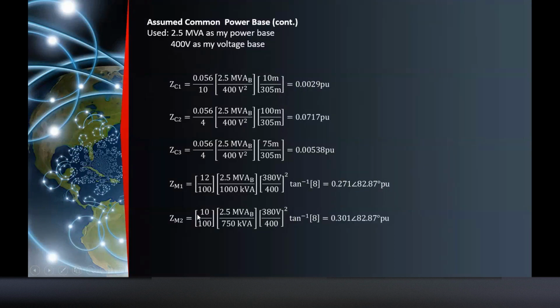For motor 2, the subtransient reactance is 10 divided by 100, multiplied by 2.5 MVA as your base, divided by 750 kVA or 750 horsepower. We are just converting again, multiplied by 380 volts divided by 400 volts squared. Then for the short circuit power factor, you will get the inverse tangent. You will get 0.301 angle 82.87. So everything has now been converted to per unit.